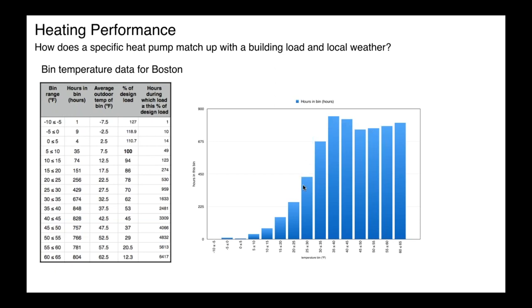And that's good news from the standpoint of heat pump performance. It simply is showing you that the heat pump in this particular location is going to be operating many more hours in the, let's pick a bin, 30 to 35 degree range compared to when it's in the 5 to 10 degree range, okay? So the more hours we have under those moderate temperatures, the higher our capacity is, which means less runtime, and also the higher the coefficient of performance is going to be.